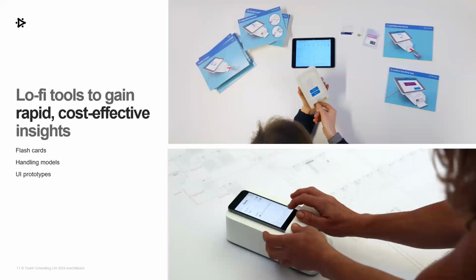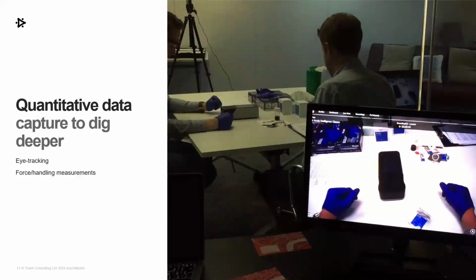and printed instructional material. And in addition to HF and design, we had mechanical and electronics and software engineers observe some of the case studies, which we found very important. Interesting to note that the UI workflow we found impacted the physical device design and vice versa. So, for example, we needed a lockout on the door while the sample test was being run. So the next slide gives another example of some qualitative methods that we used during this project.